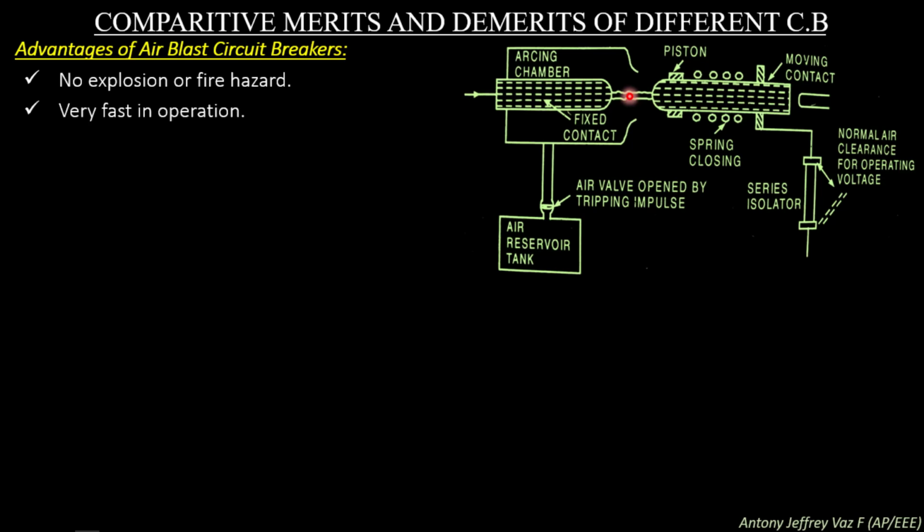Very fast in operation, since compressed air present in the air reservoir is used to trip the circuit, that is, to operate the moving contact, so very fast operation is attained. Suitability for rapid reclosing, since a spring system is used, so the moving contacts can be reclosed at a fast rate, the same as the opening rate.